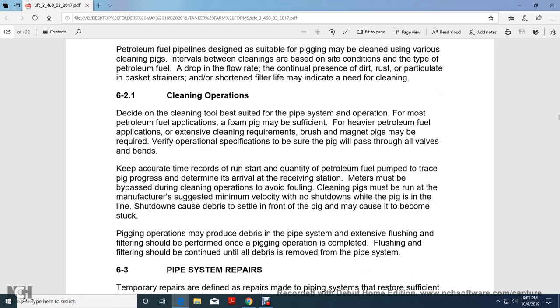6-2.1, cleaning operations. The size of the cleaning tool will be best suited to the piping system and the operation. For most fuel applications, a foam pig may be sufficient. Heavier petroleum fuel applications or extensive cleaning requirements. Brushes and magnet pigs may be required. Check the operational specification to be sure the pigs will pass through all of the valves and bends.